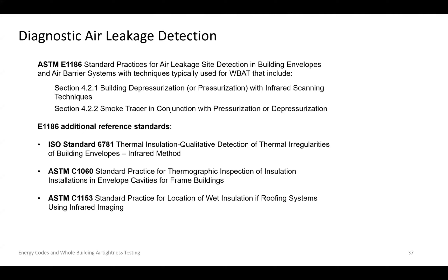So thermal infrared, you have to make sure you've got somebody that is properly certified. They have to be a minimum NDT level 2, and they have to be supervised by an NDT level 3 who's also validating procedures. So there's a lot of folks running around out there who don't have minimum levels of qualification and don't know how to differentiate between a relevant and non-relevant indication. And this is all part of what's picked up in the pre-qualification test.